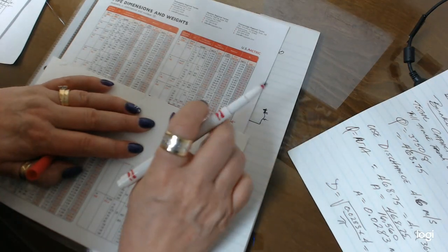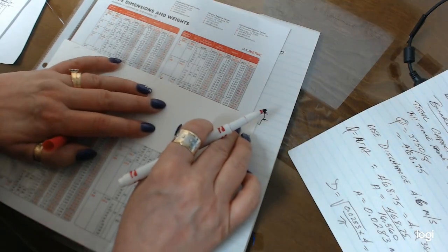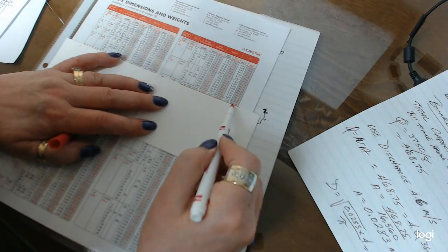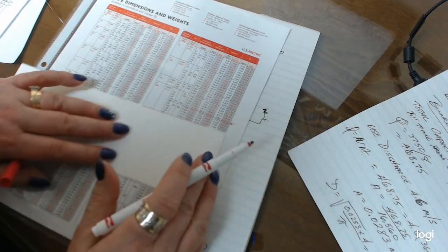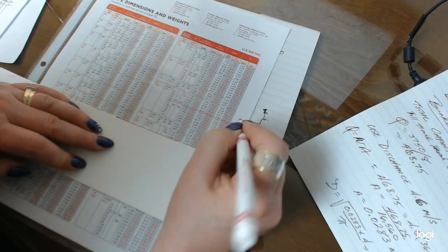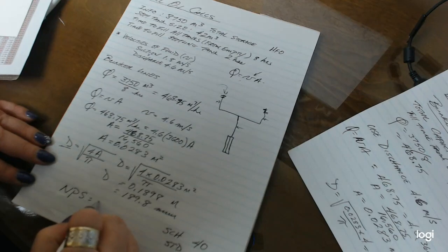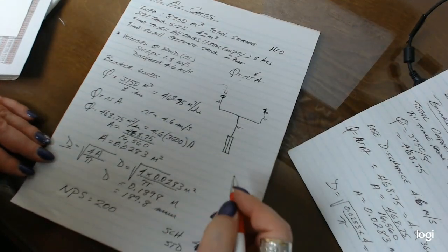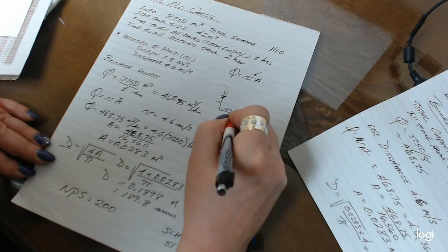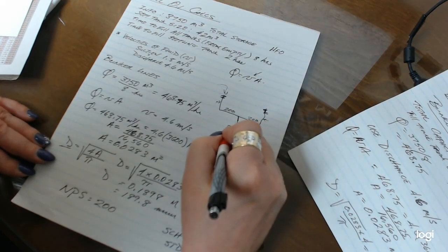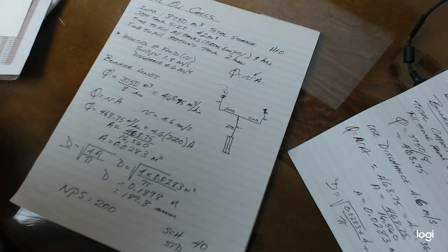but will be adequate, because if I use the first one up, the standard pipe is a little bit too small. It's 178. Now I know it's very difficult for you guys to see that, but I want you to try this on your own. So in this particular scenario, I would use an NPS of 200 millimeters. So when I put that on my diagram, that would say 200, 200, and 200 right here. And that is how we size the bunkering lines. I will update you again shortly for how to create sizes of piping for our transfer lines. Thanks.